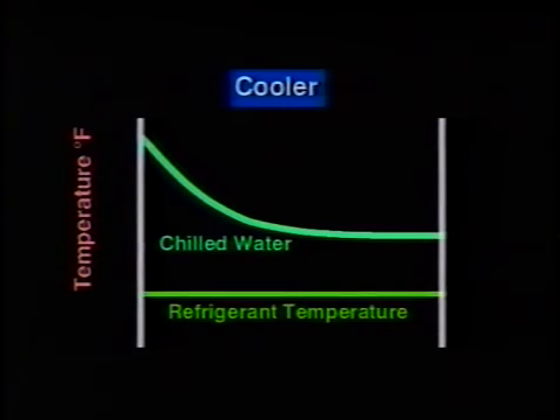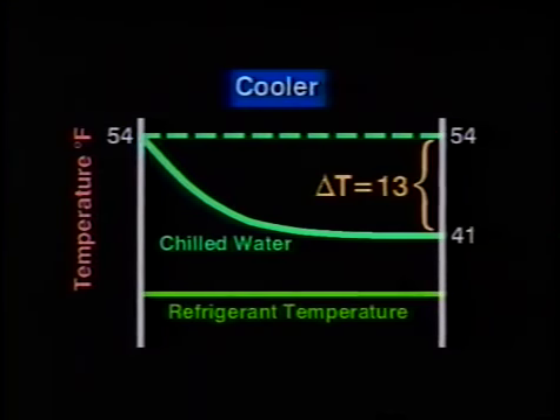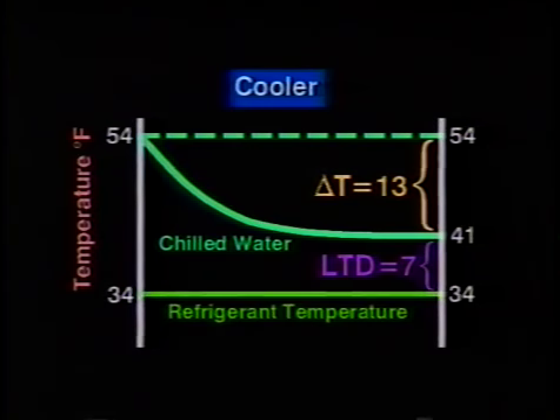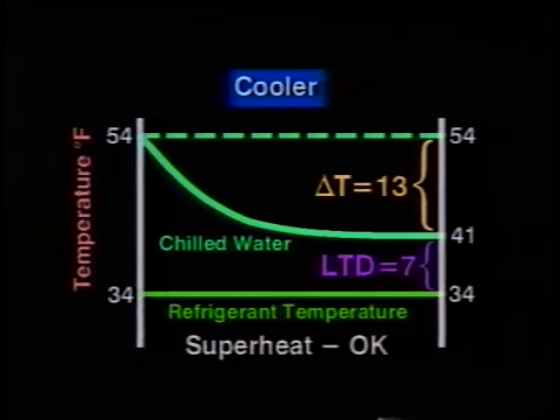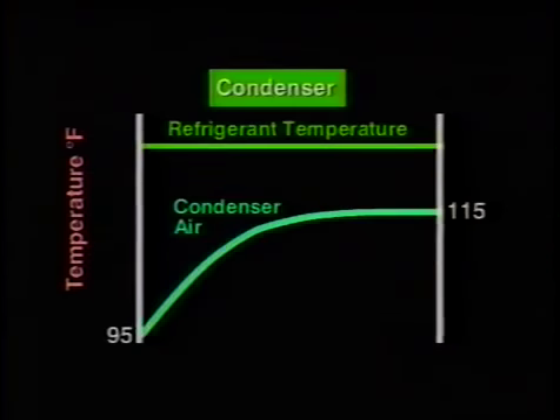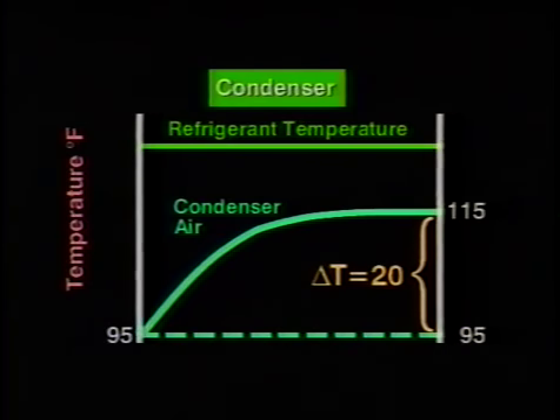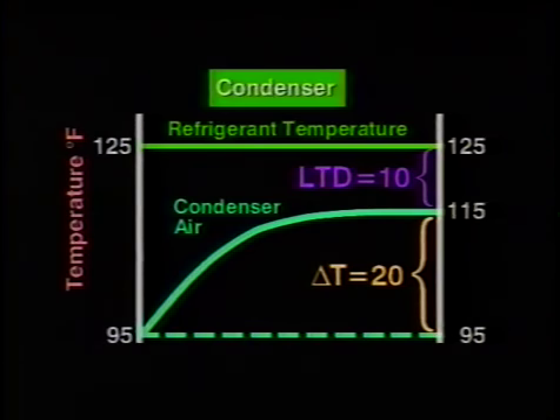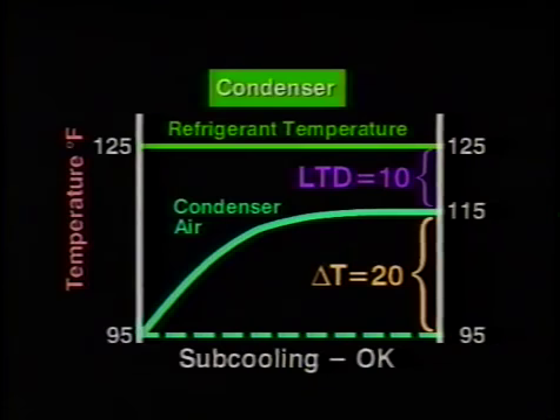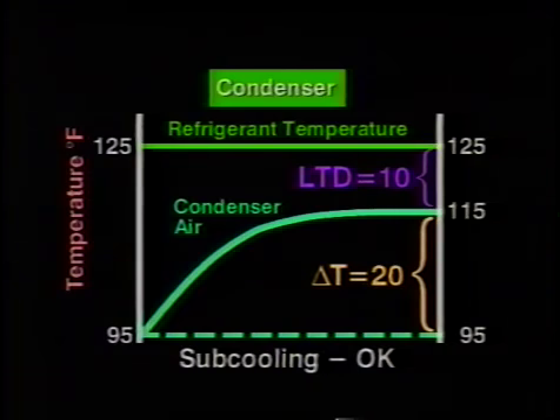The chilled water in and out is 54 degrees and 41 degrees for a delta T of 13 degrees Fahrenheit. The saturated cooler temperature is 2 degrees low at 34 degrees, giving us an LTD of 7 degrees. The suction superheat is normal at 11 degrees. The delta T of the air across the condenser shows it's below design with a 20 degree Fahrenheit rise and the saturated condensing temperature is 125 degrees. The subcooling looks okay, so it appears that the condenser is doing its job. It's just not loaded fully.